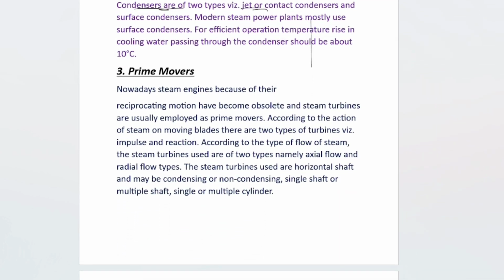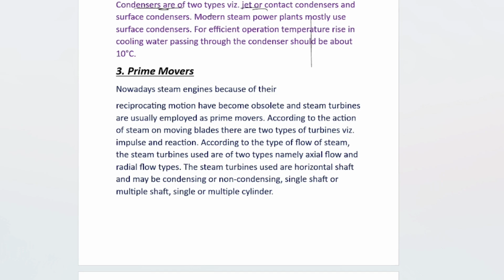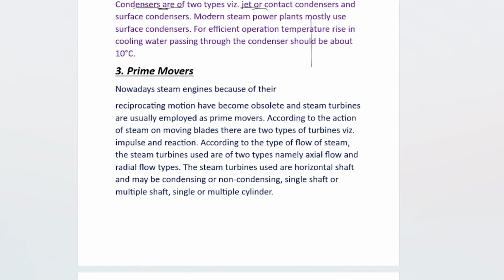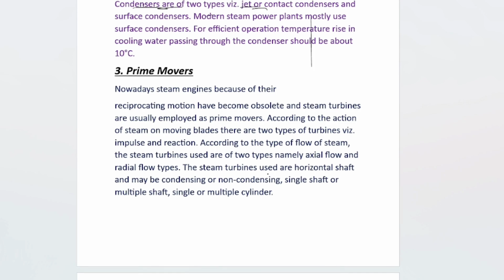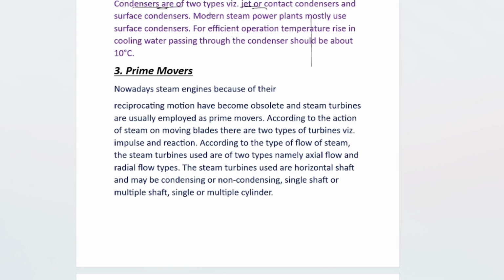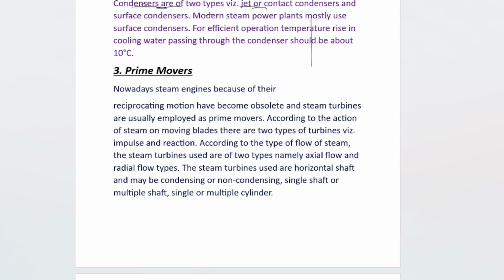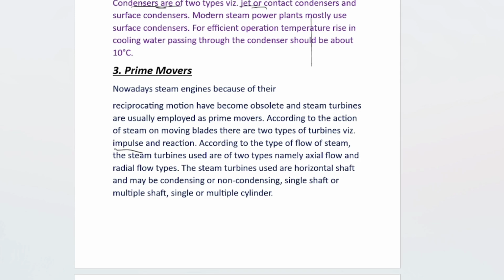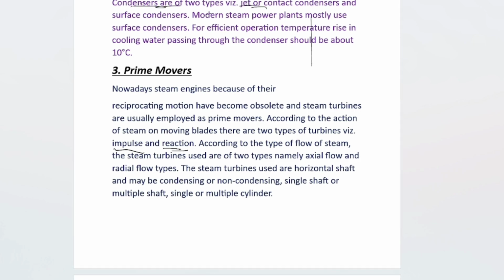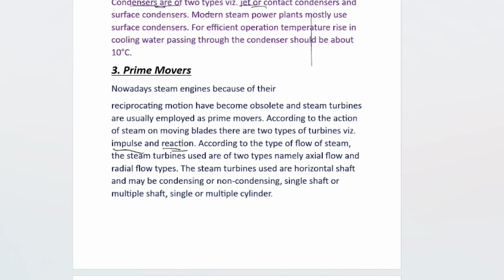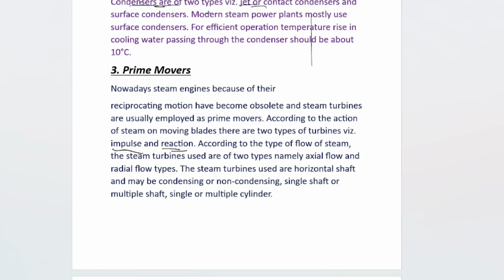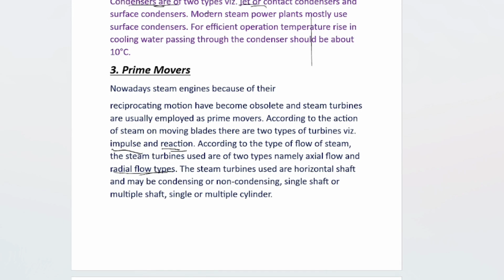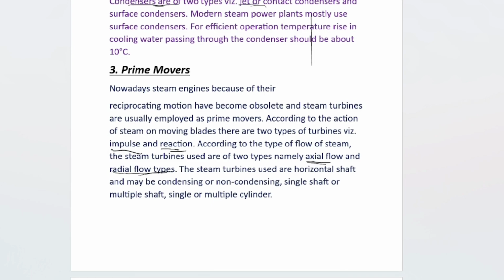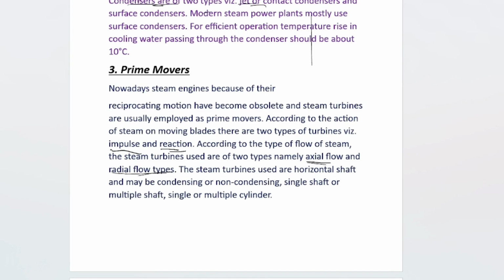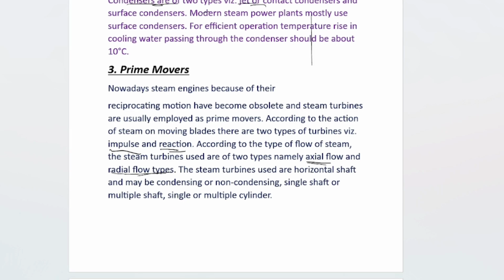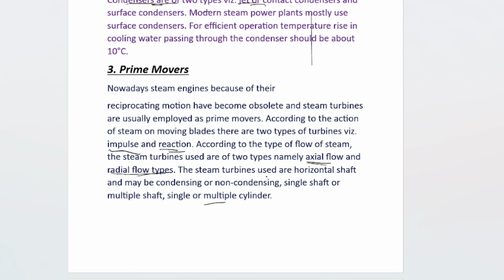The third main part is the prime mover. Nowadays steam engines, because of their reciprocating motion, have become obsolete, and steam turbines are usually employed as prime movers. According to the action of steam on the moving blades, there are two types of turbines: impulse and reaction. According to the type of flow of steam, the turbines are axial flow and radial flow. The steam turbines used have a horizontal shaft and may be condensing or non-condensing, single shaft or multiple shaft, single or multiple cylinder.